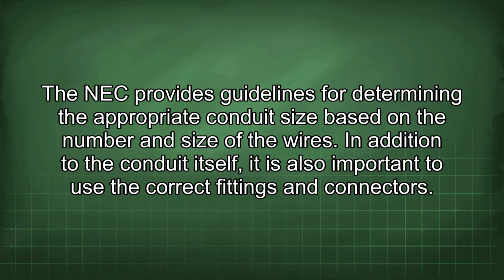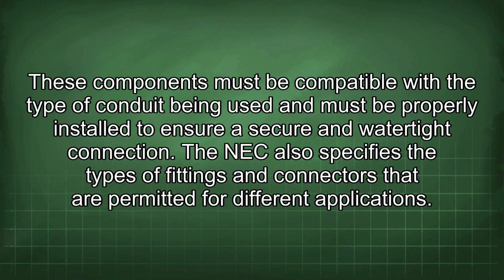The NEC provides guidelines for determining the appropriate conduit size based on the number and size of the wires. In addition to the conduit itself, it is also important to use the correct fittings and connectors. These components must be compatible with the type of conduit being used and must be properly installed to ensure a secure and watertight connection. The NEC also specifies the types of fittings and connectors that are permitted for different applications.